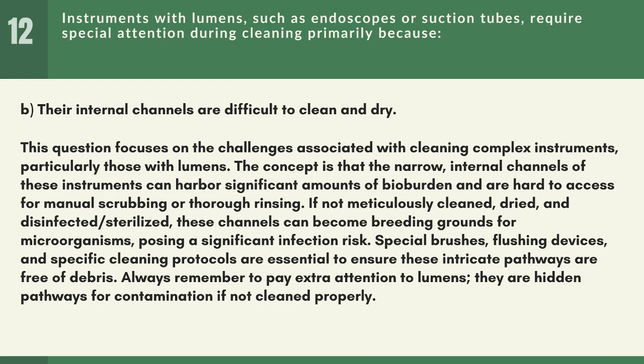Answer: B. Their internal channels are difficult to clean and dry. This question focuses on the challenges associated with cleaning complex instruments, particularly those with lumens. The concept is that the narrow, internal channels of these instruments can harbor significant amounts of bioburden and are hard to access for manual scrubbing or thorough rinsing.